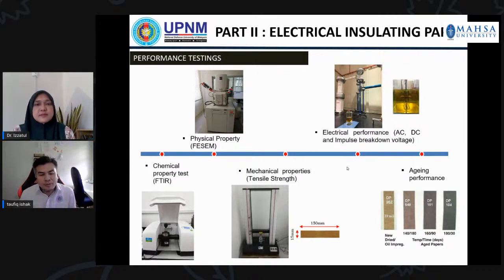The first one is to check the chemical properties of the paper that we produce, and then we check the physical properties using the FESEM. The most important thing for a good insulation paper is very high tensile strength, so we test the mechanical tensile strength. Then, of course, the electrical performance, similar to oil: we need to test the AC, DC, and impulse breakdown voltage for this new kind of insulation paper. And the last and most important part is the aging performance, especially over longer periods for application inside the transformer.